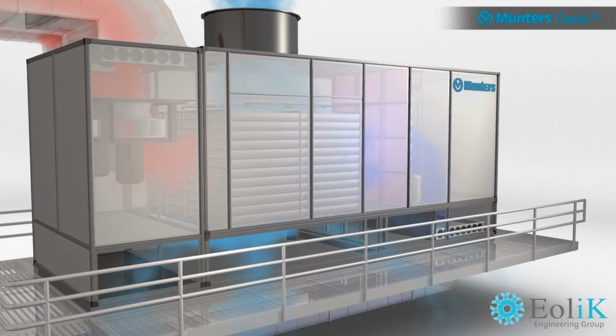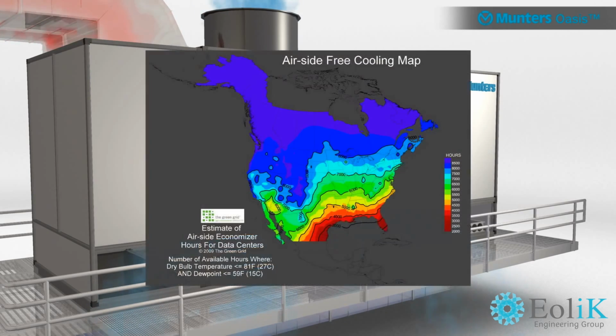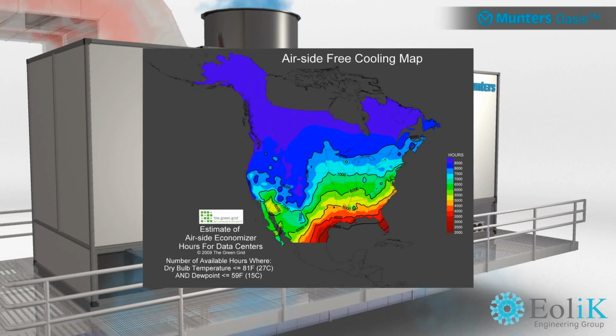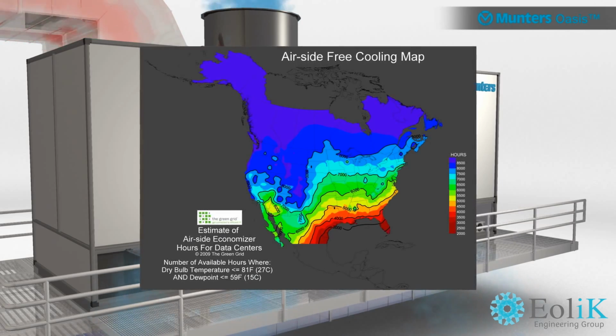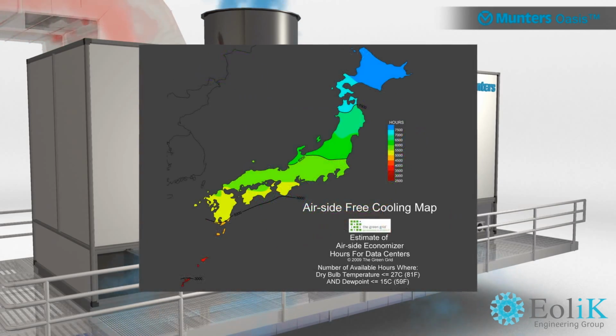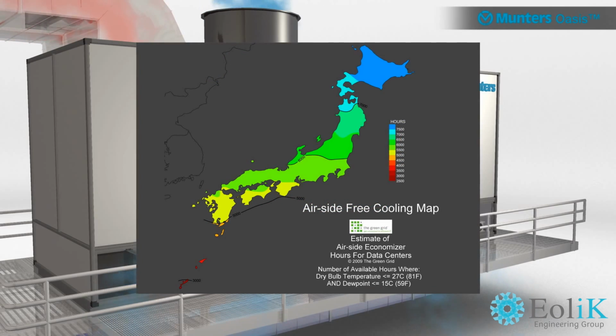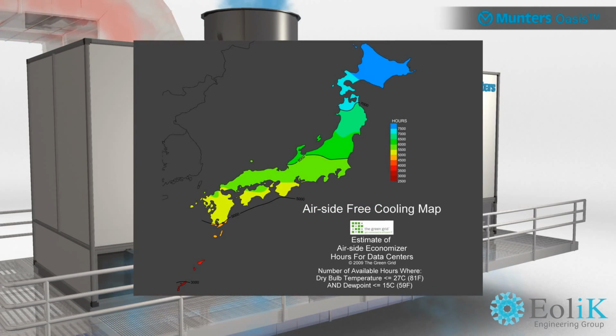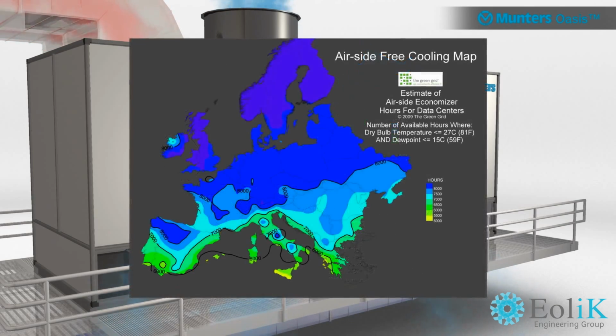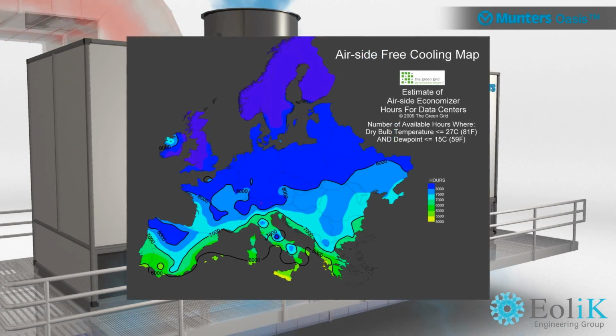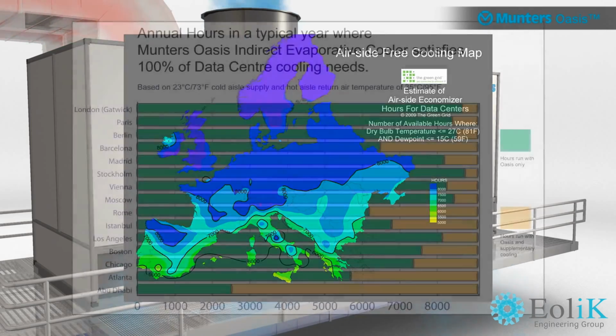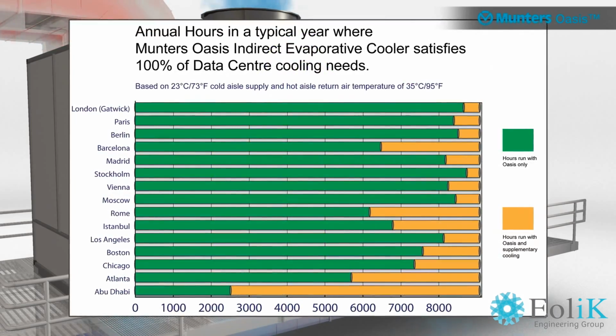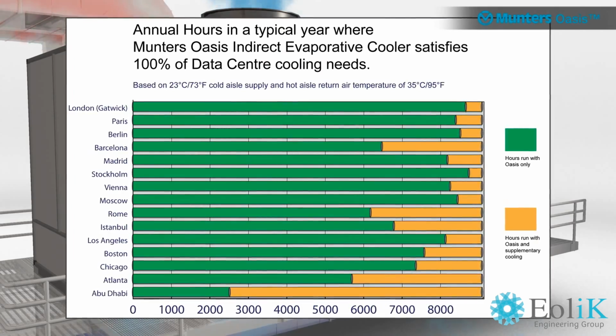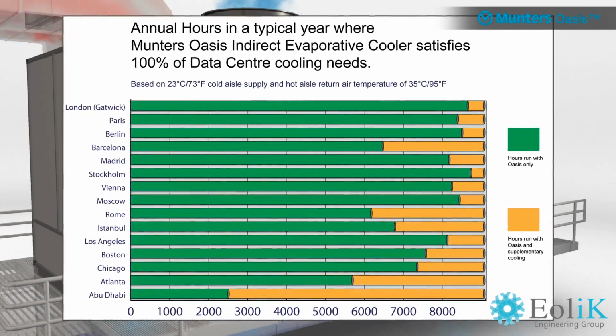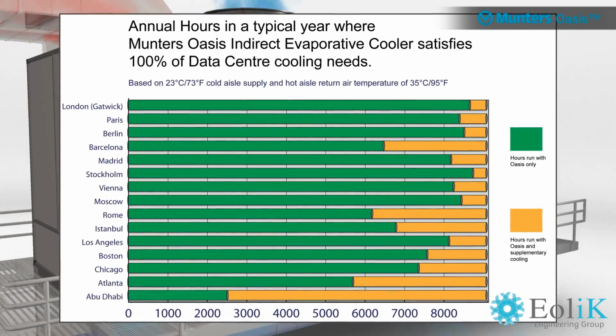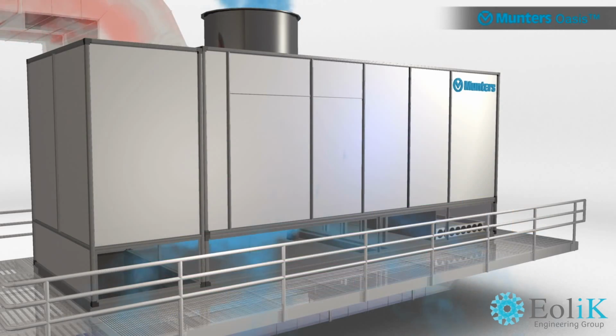Power usage effectiveness, PUE, is a measure of how efficiently a computer data center uses its power. Specifically, the ratio calculates how much power is actually used by the total facility and divides this by the IT power. The average data center PUE is 2.0, and a facility with a PUE of less than 1.2 is generally considered to be very green. The remarkable efficiency of the Oasis indirect evaporative cooler allows operators to achieve PUE ratios significantly lower than this green standard, with some plants now dropping below 1.1.